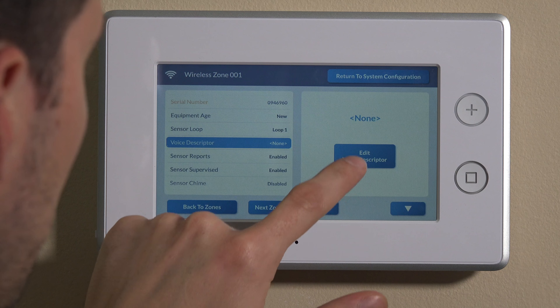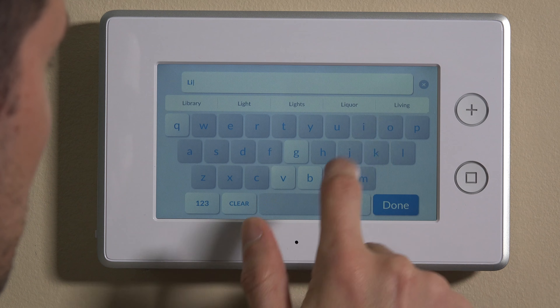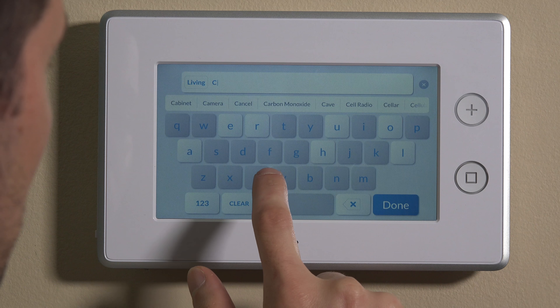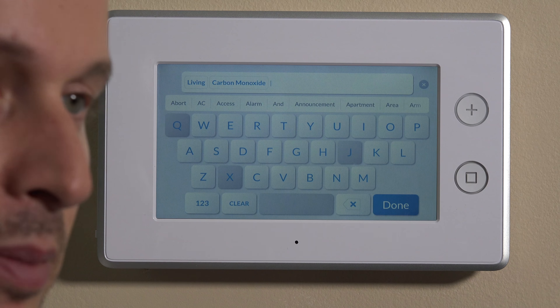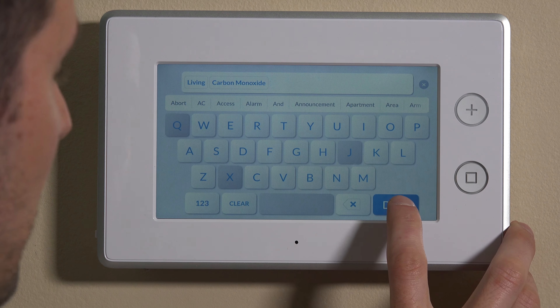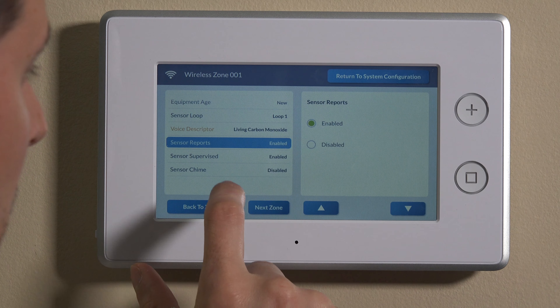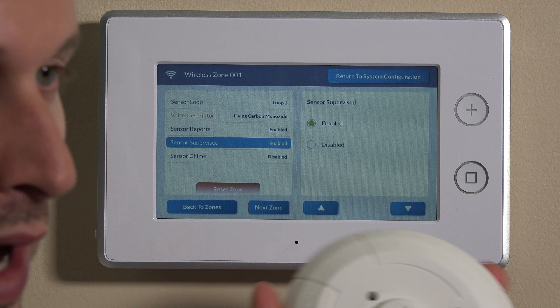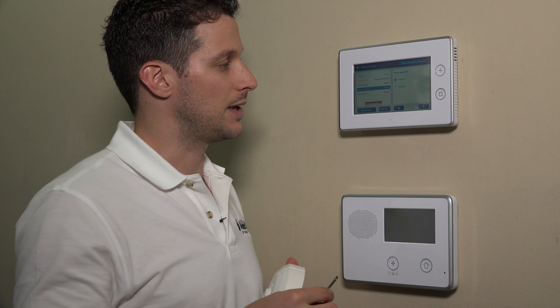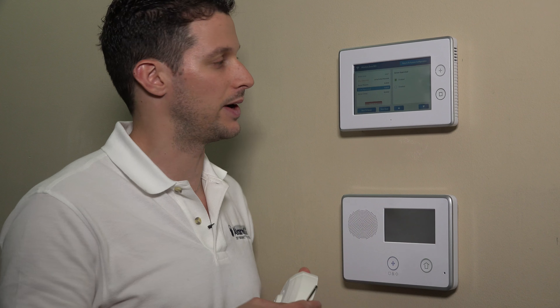Keep that on loop one. The voice descriptor we can change to wherever it's located in the home. This one for us is in the living room, but we'll put this as carbon monoxide in the living room — that's a new added selection, so it will voice enunciate when that occurs. We can now hit done and move down. We always want the CO detector to report to the central station, so we want to keep sensor reports enabled. Sensor supervision — we always want to supervise this and make sure it is communicating with the panel. If it ever does not ping back during a supervisory interval, it will trigger a trouble, and we can remedy the issue or move the detector to a better area for improved signal.